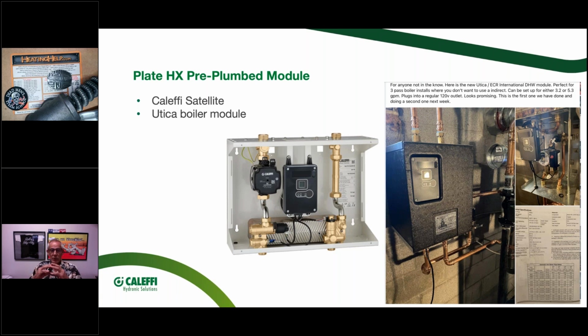What happens is when you have a hot surface area, like running the A side of that heat exchanger hitting it with 190-degree water, the minerals in the water really precipitate out, really get attracted to that high surface temperature on the plate, and that's where you see the fouling.